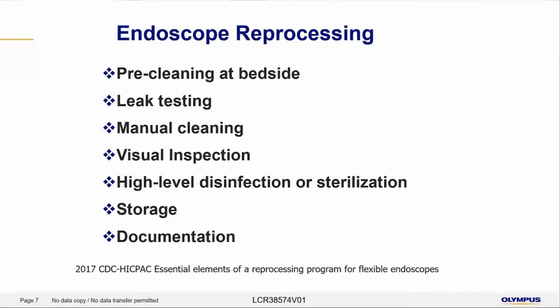to ensure there is no visible damage, high-level disinfection or sterilization to kill any organisms that may remain on the scope after the cleaning process has been completed, and finally, storage to ensure that a reprocessed endoscope is kept clean and out of harm's way before the next clinical use. Documentation, as we all know, is also an important step in the overall process.